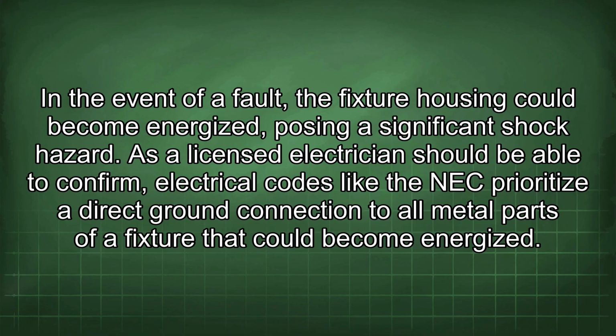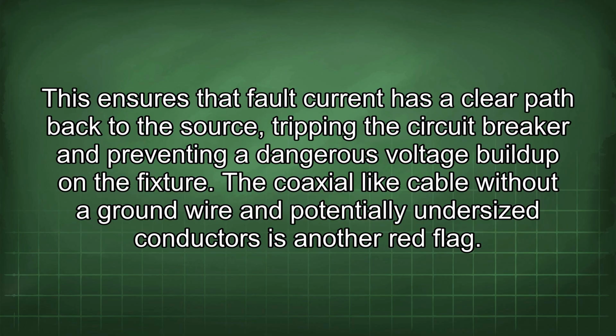As a licensed electrician should be able to confirm, electrical codes like the NEC prioritize a direct ground connection to all metal parts of a fixture that could become energized. This ensures that fault current has a clear path back to the source, tripping the circuit breaker and preventing a dangerous voltage build-up on the fixture.